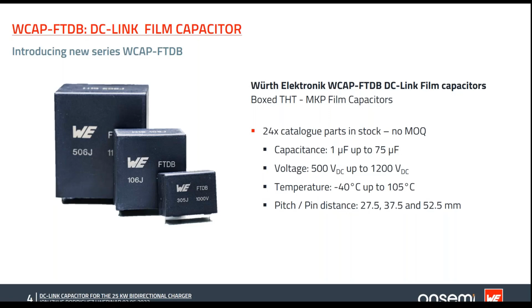The term MKP, which was part of the series name, means that the capacitor is made with metallized polypropylene film. This is the plastic film acting as a dielectric, and a thin layer of aluminum is deposited on one side of the dielectric to form the electrode. Two films like this are rolled together, and we create this kind of capacitor. Polypropylene materials provide very stable capacitance characteristics, as well as very long life and self-healing properties against the holes that are created inside of the dielectric when you have a surge voltage.